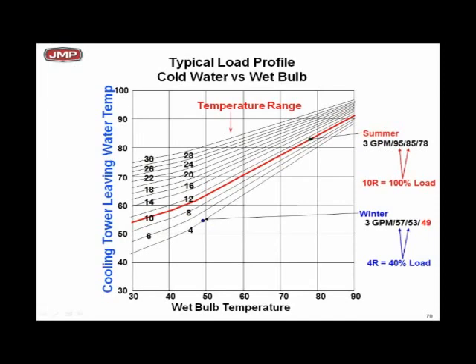One thing that I wish I had an hour to do with this one slide, so humor me for just a minute. That red line is a constant load or temperature range. In this case, it's 10 degrees. So that red line on the slide gives you a constant load in tons on your tower, whatever it may be. The bottom axis is the wet bulb.